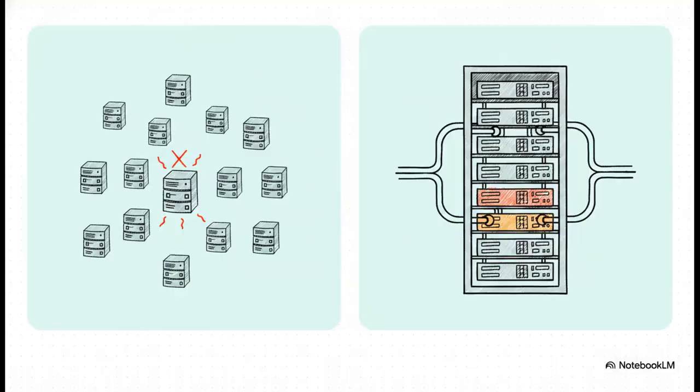AI infrastructure racks. To put that into perspective, in traditional flat list management, an alert just tells you server X is running hot. Okay, but you have almost no context. With rack scale context, though, that alert tells you that multiple systems in, say, rack Y are heating up, and it directly correlates this to a specific coolant distribution unit or PDU. This means operators can take emergency action on entire groups of racks if a CDU leak is detected. For AI infrastructure, having that exact physical context is absolutely vital.